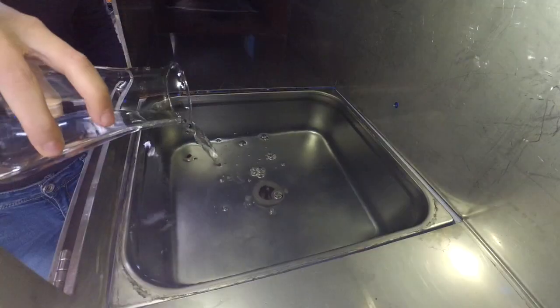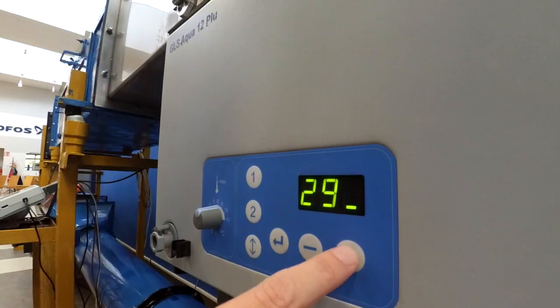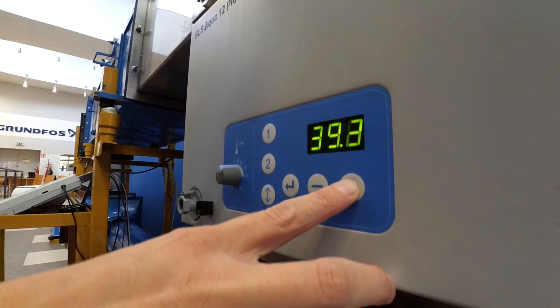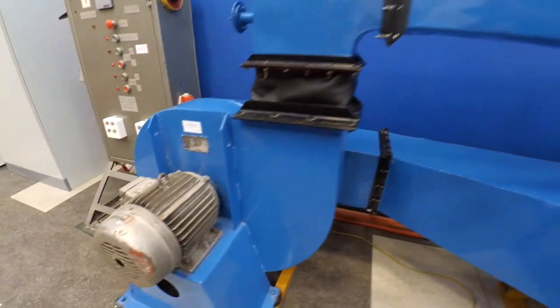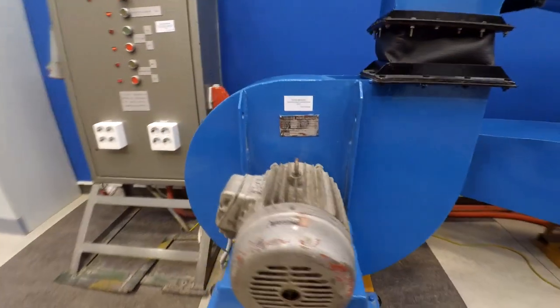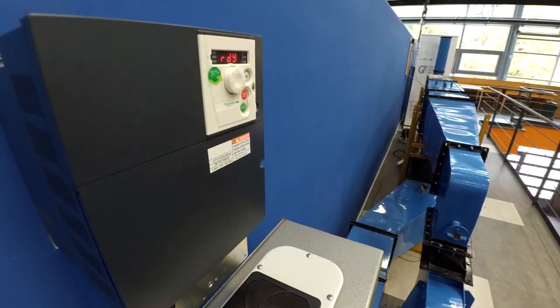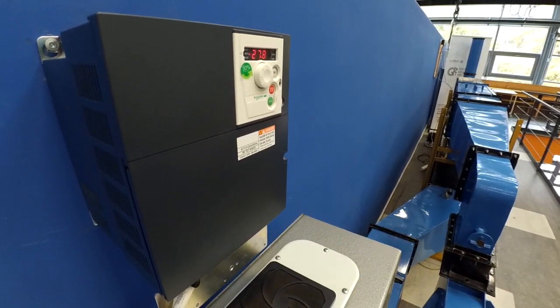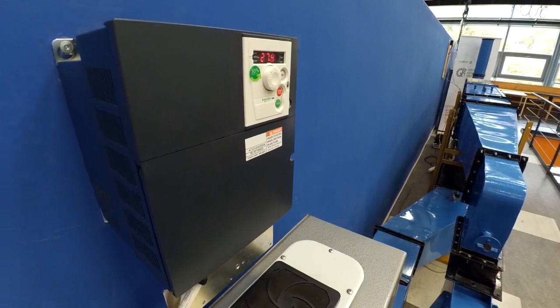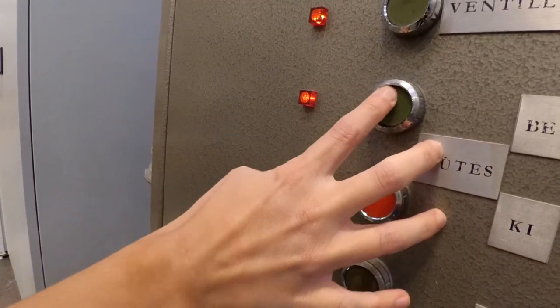The liquid used for evaporation is contained in a thermo vessel, the temperature of which can be freely adjusted to the desired value. The air is circulated by a radial fan, where the air velocity can be adjusted by controlling the speed of the fan, using a frequency converter. The air temperature can be controlled by an electric heating unit.